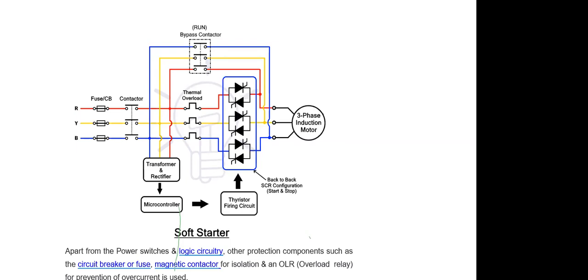Now, how the soft starter operates: it's again a reduced voltage start. As far as my consideration is concerned, I still feel it's like a DOL start, but in the DOL start you apply full voltage on the motor. Here you have the option to reduce that voltage when it is getting started, so a reduced voltage start with a timing close to a DOL starter. In a soft starter, there are options to chop the voltage. Chop means if it is 415, you can program it to 200 volt. Initially that will be applied, then gradually as it starts, it will go to 415.